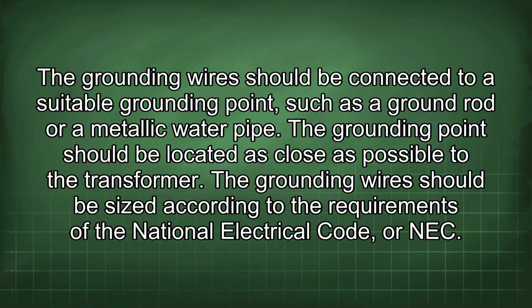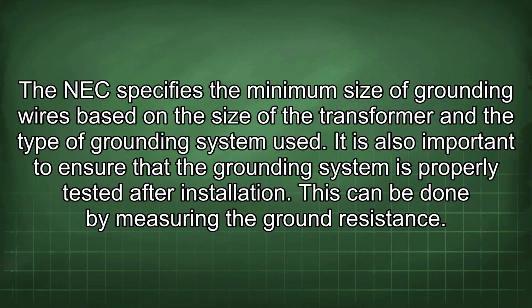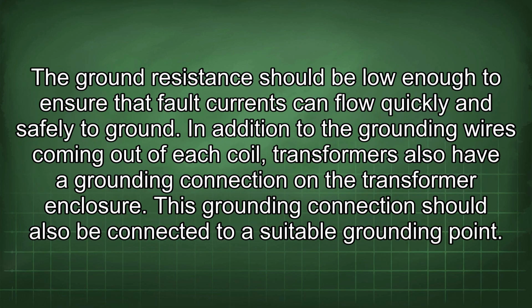The grounding wire should be sized according to the requirements of the National Electrical Code, or NEC. The NEC specifies the minimum size of grounding wires based on the size of the transformer and the type of grounding system used. It is also important to ensure that the grounding system is properly tested after installation. This can be done by measuring the ground resistance. The ground resistance should be low enough to ensure that fault currents can flow quickly and safely to ground.